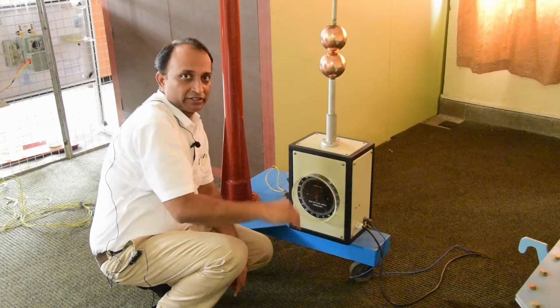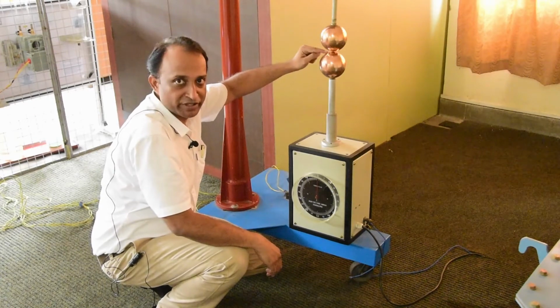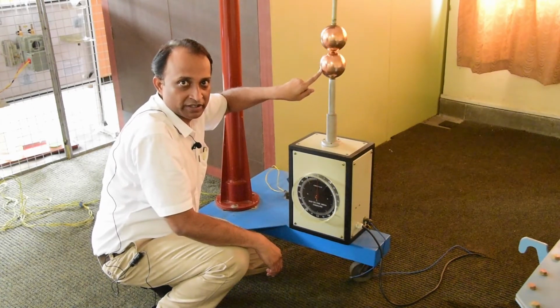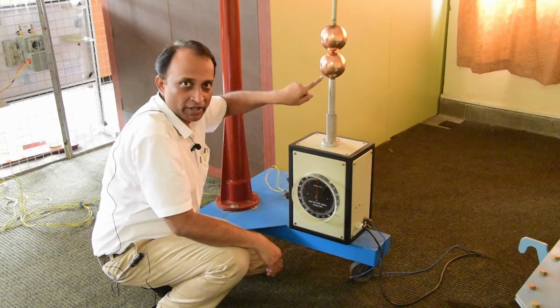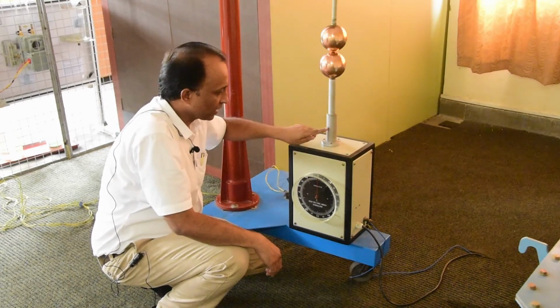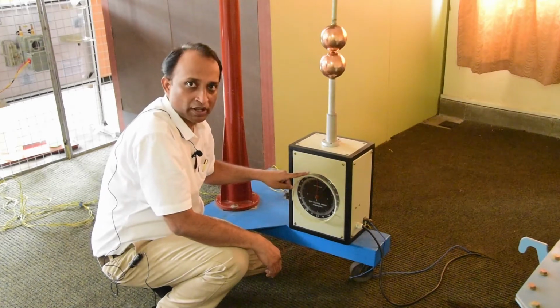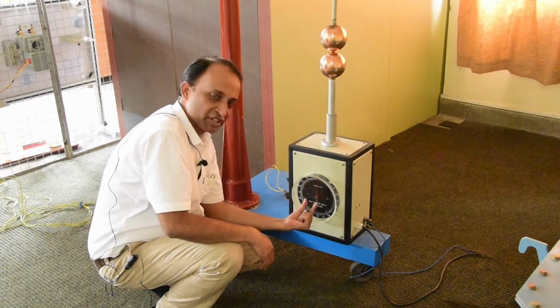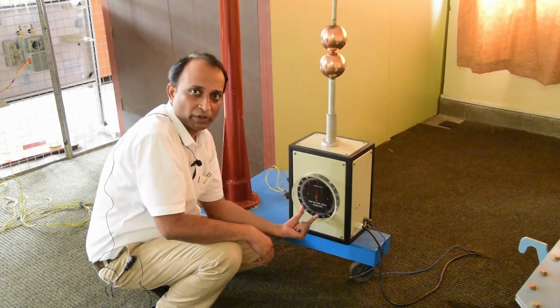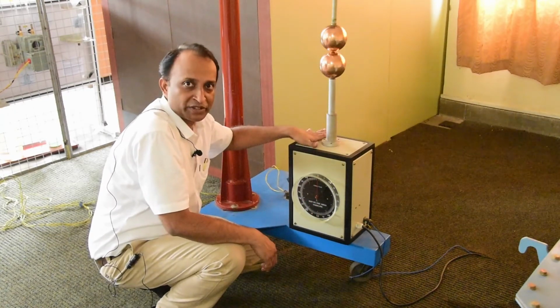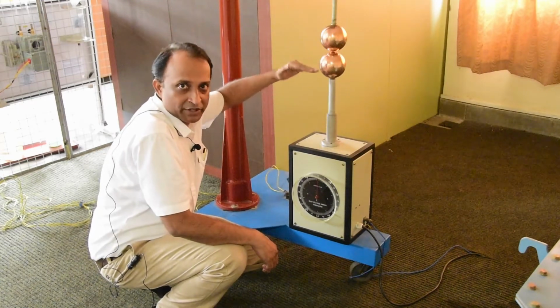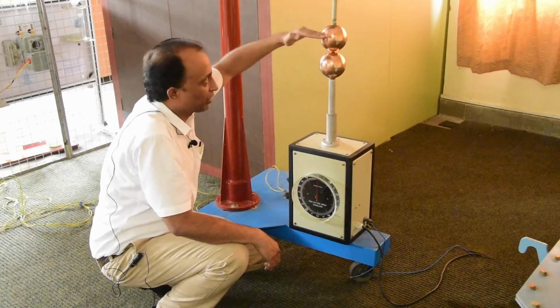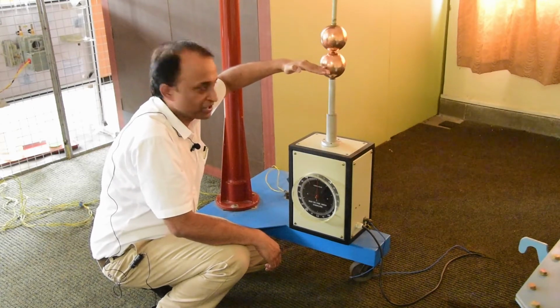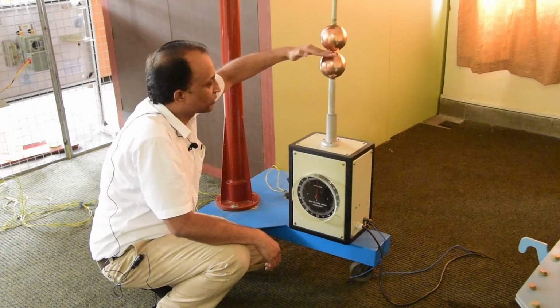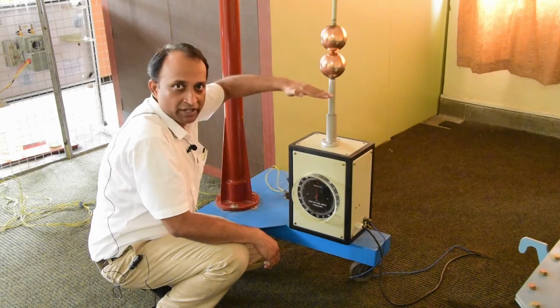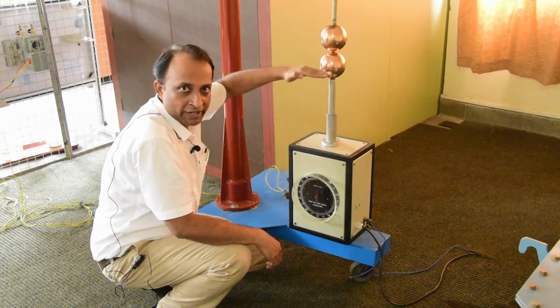There is a sphere gap, an air gap in between these two, and then this is the second electrode, that is the lower electrode. This is connected to a motorized control along with a position showing dial. There is a motorized controller inside which is able to adjust the spacing between the two electrodes. The upper electrode is fixed, but the spacing between the two electrodes, that is the air gap spacing, can be adjusted by vertically adjusting the position of the lower electrode.